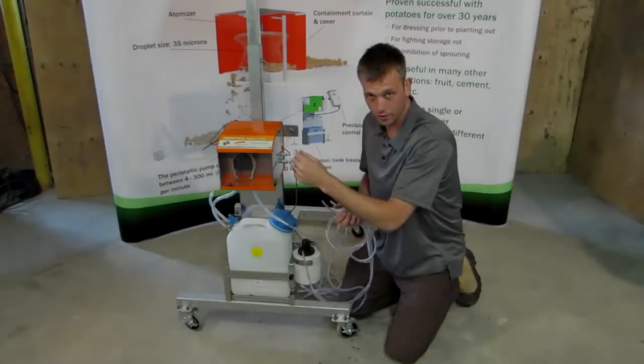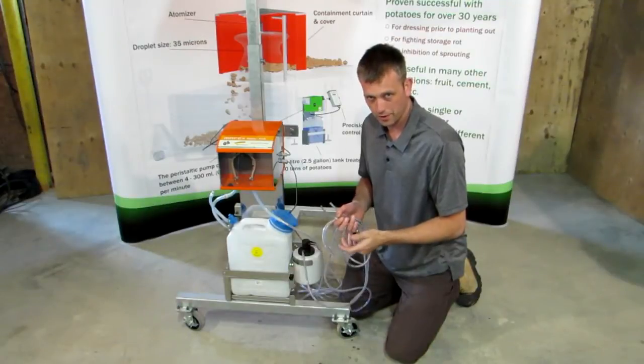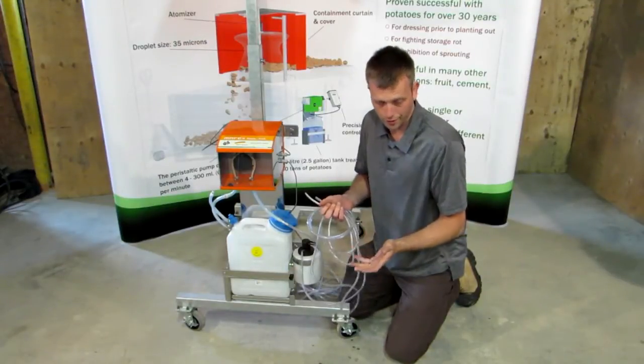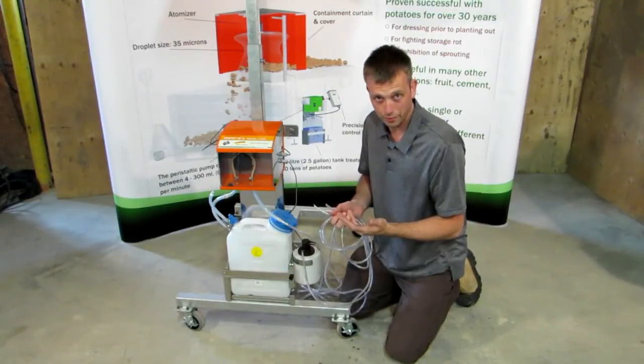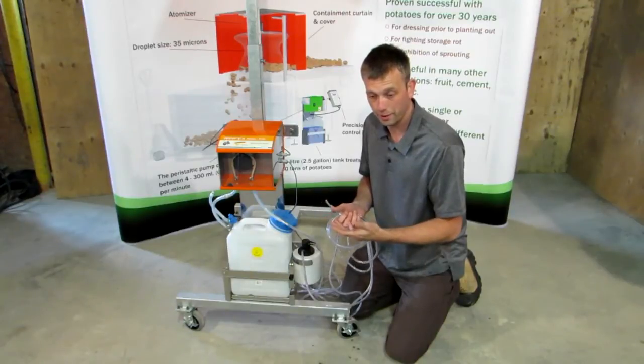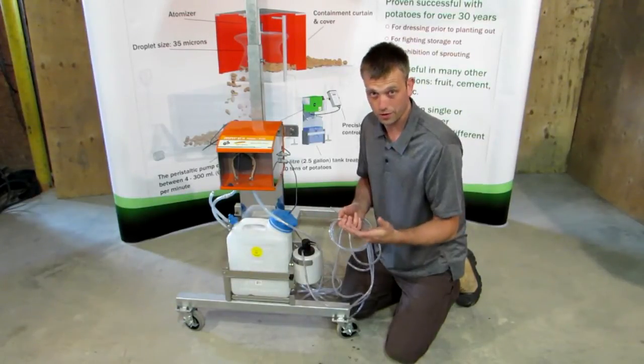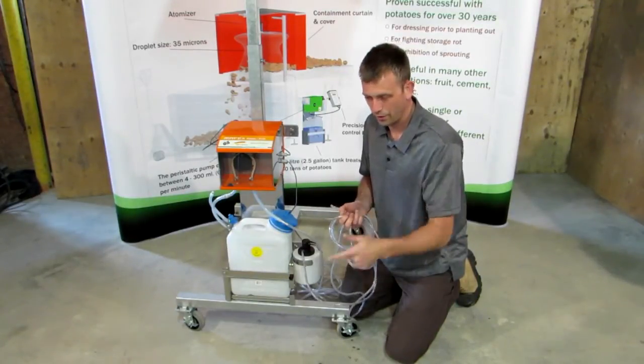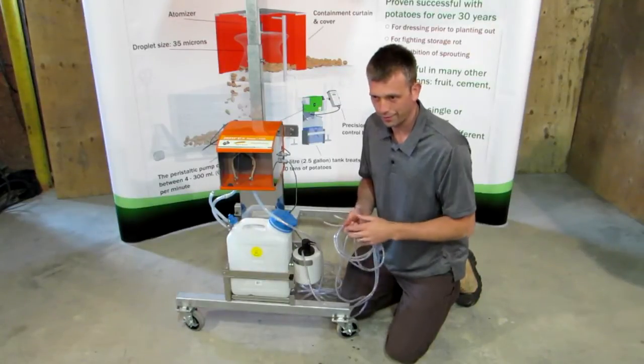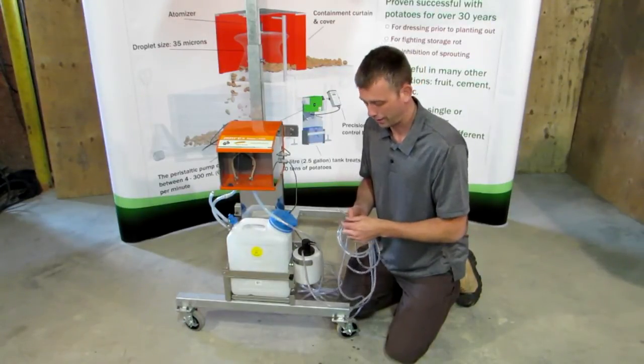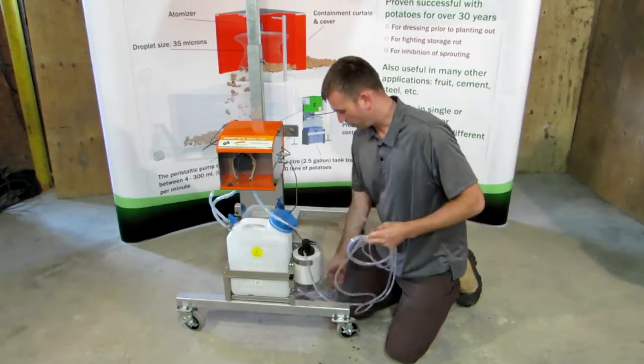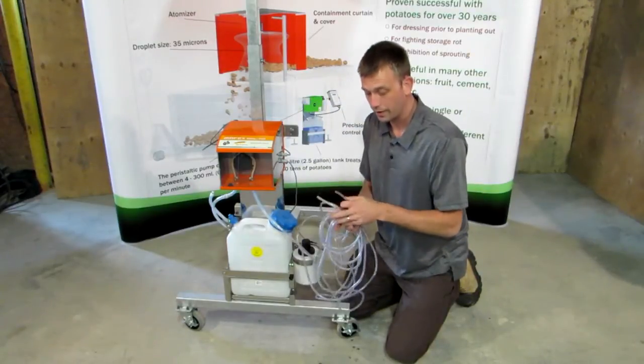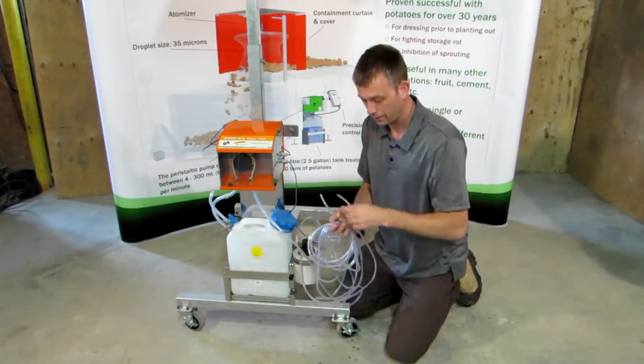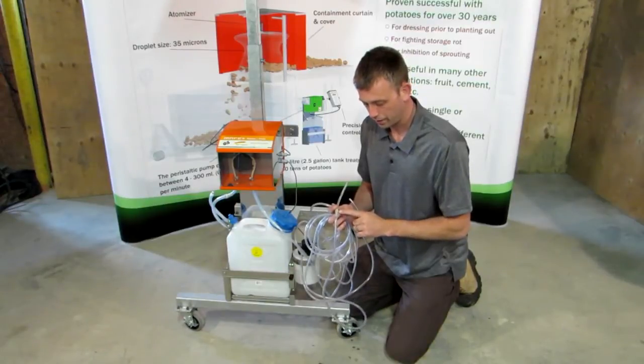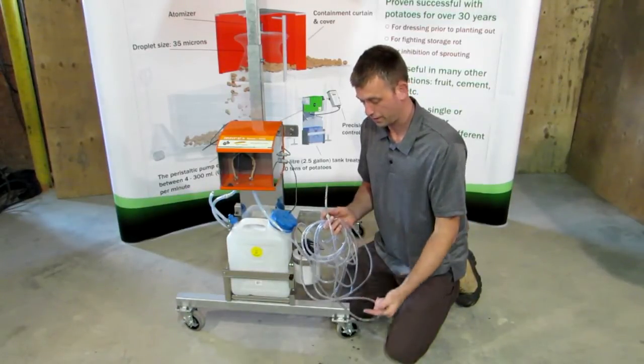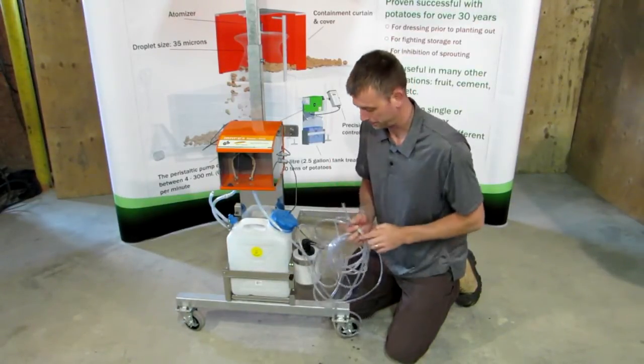As you're stringing the hoses, shorten them up as much as you can. The shorter they are, the quicker the whole system will fill up with liquid and it will start spraying. And also, if we're using the flow sensor, if there's no extra loops, there's no places where air bubbles can get caught or anything like that. So we'll string both these hoses through into this Y piece and make sure that the one-way valve is pointing the correct direction.